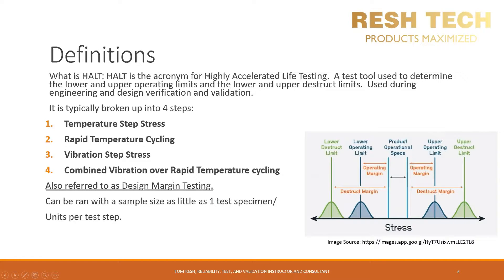Let's go ahead and define HALT. What is HALT? HALT is Highly Accelerated Life Testing. It is a tool used to determine the lower and upper operating limits and the lower and upper destruct limits for your product or system. It is used during the engineering design verification and validation stages. It is typically broken up into four steps: the temperature step stress, rapid temperature cycling, vibration step stress, and combined vibration over rapid temperature cycling. The bottom right-hand of the screen displays the parameters that we are trying to determine or confirm for our design.